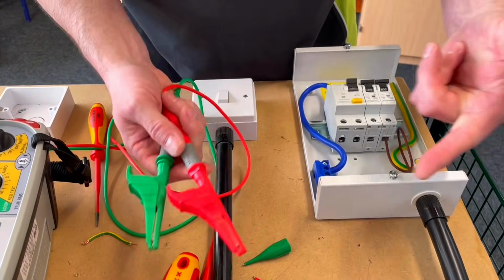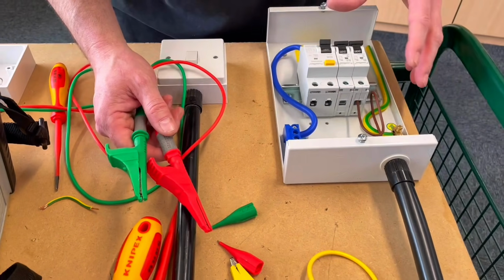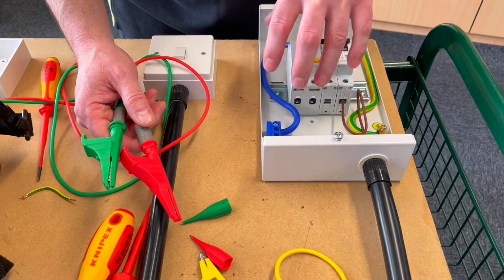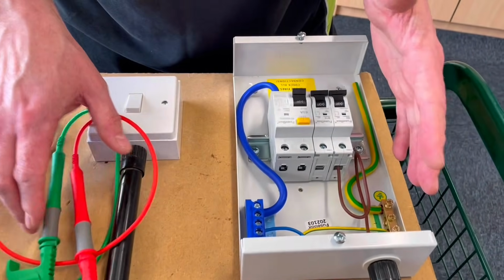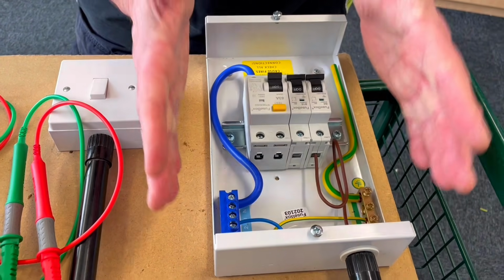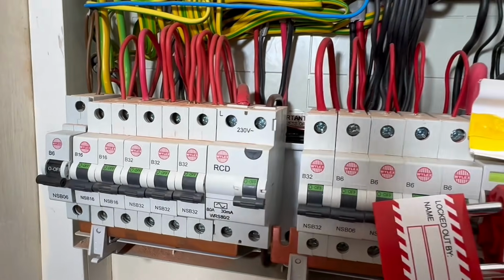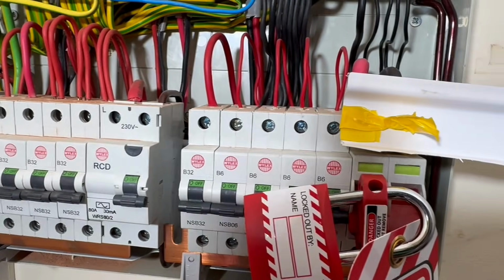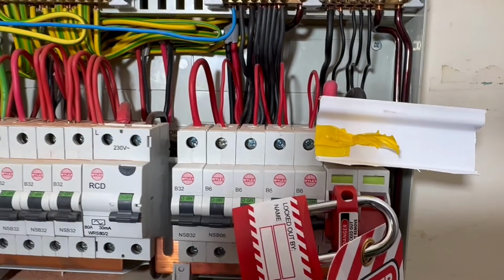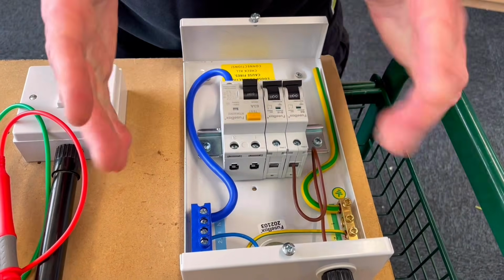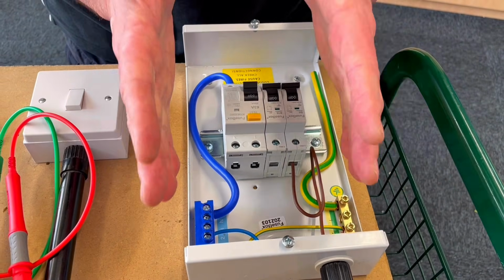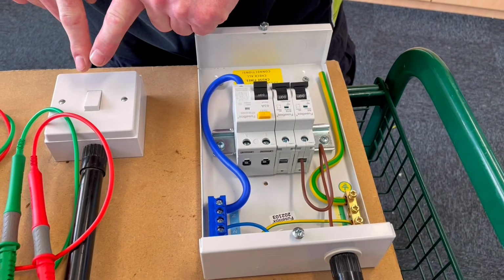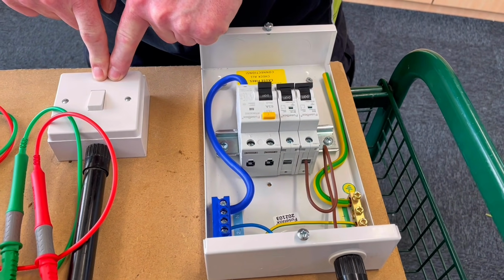I'm going to change between tips and probes, but let's look at the consumer unit first. Now, we haven't got the tails in here. We know the installation is completely dead. This is an early test that we're carrying out. If it was a board that was energized when you arrived, there's tons of safe isolation procedures before you carry out this test. But let's think about the things that we must make sure are in place before carrying out this test. We said that the switches, and there's only one in circuit, need to be left on.